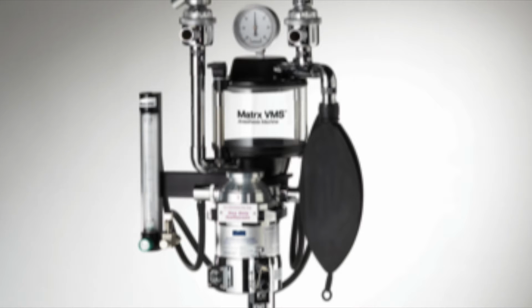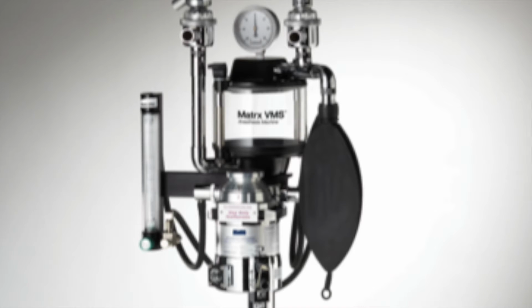When the valve knob is turned in a counterclockwise motion, oxygen enters from the bottom of the gas column and exits at the top, pushing the ball indicator within the column. The oxygen flow is measured in liters per minute and is indicated by viewing the ball at the widest part, the middle.